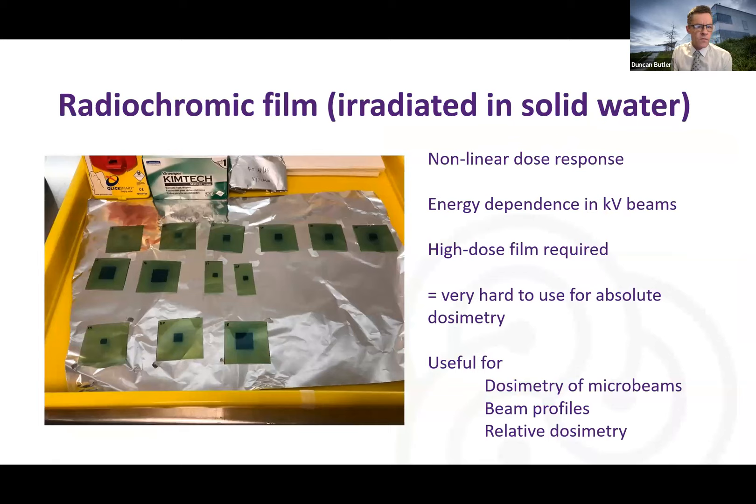Radiochromic film. Personally I've failed to use that for dosimetry. I know other people have had some success, but generally it's quite non-linear, has an energy dependence. You can't use the normal EBT3. You have to use a high-dose film and that's less uniform. So I've found it very hard to use for absolute dosimetry. But it's really good for getting profiles of microbeams, beam profiles, and relative dosimetry.